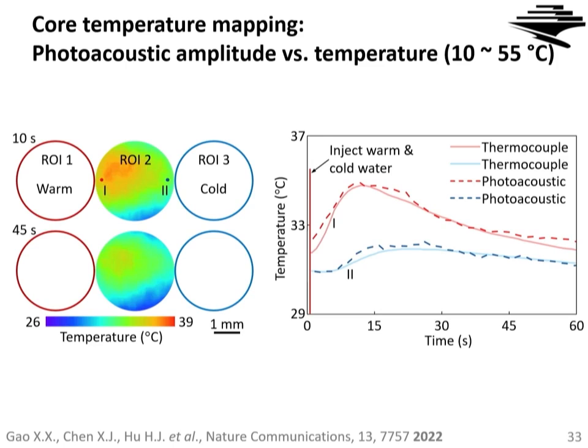And the photoacoustic signals are proportional to the core body temperature. This is a 3D mapping result. In the phantom, you can see the warm region, the cold region, and somewhere in the middle is a gradient. After a few seconds, you can see that it becomes more uniform. We inserted 2 thermocouples, and you can see the thermocouple reading and the photoacoustic reading match each other very well.